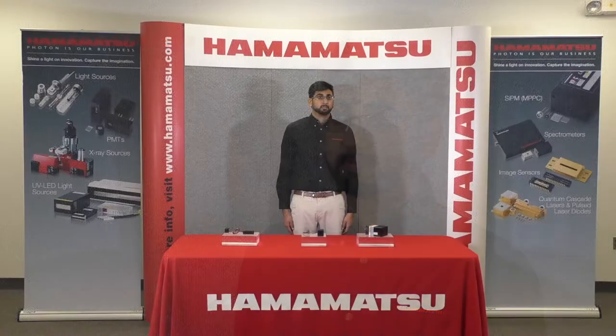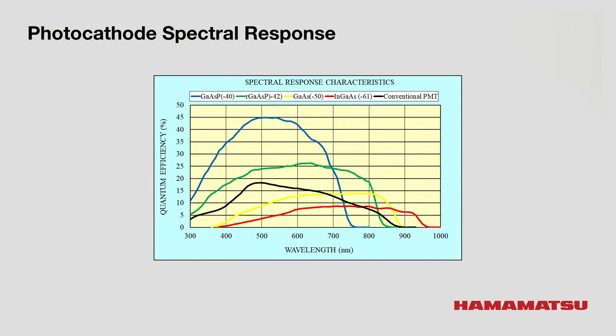The main differences between each are the sensitivities at different wavelength ranges. As you can see here, GaAsP has a peak quantum efficiency of 45% for visible wavelengths, GaAs has over 10% quantum efficiency between 700 and 800 nanometers, and InGaAs has a high quantum efficiency up to 900 nanometers.